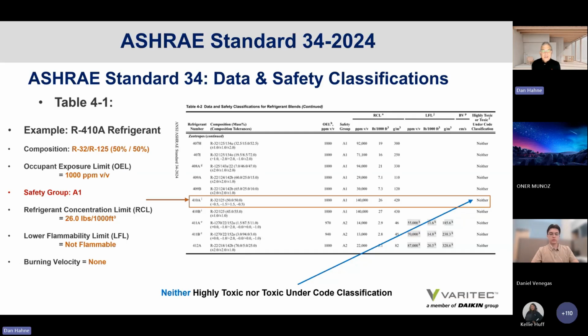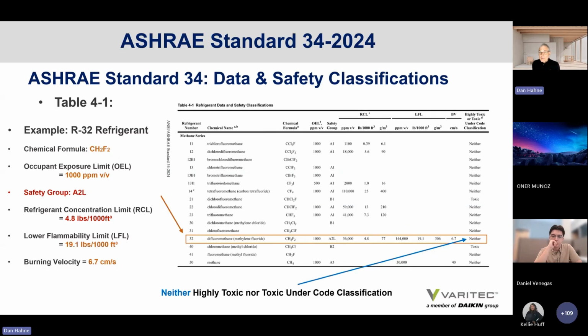So what does Standard 34 language reveal regarding the comparative nature of, let's use 3 refrigerants. Let's use a refrigerant used in variable refrigerant systems, historically R410A. R410A refrigerant is a compound refrigerant of 50% R32 and 50% R125. It has an occupational exposure limit of 1,000 parts per million by volume, and it has a safety group classification of A1. And in previous editions of Standard 15, the refrigerant concentration limit for an A1 refrigerant, or certainly R410A, was 26 pounds per 1,000 cubic feet. And because it was non-flammable, it has no flammability rating nor any burning velocity. So 26 pounds of refrigerant per 1,000 cubic feet is quite a bit of refrigerant.